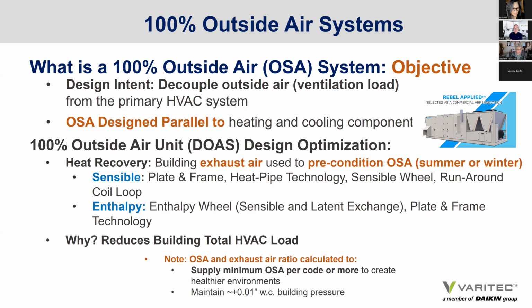And there are different technologies available today on that heat transfer solution, and it's continuing to mature and develop. There's some pretty compelling technology available today with some of our manufacturers. So by using a 100% outside air system, we want to make sure that the outside air supply flow rate is a little greater than the exhaust air rate, so a building's pressure is always positive to the outdoors, because if you have negative pressure in a building, you'll suck in either very cold air at our coldest times of year or very warm, hot air at our high times of year.